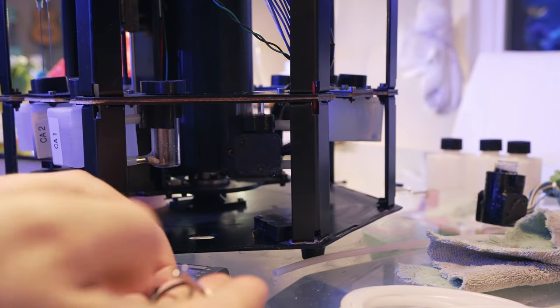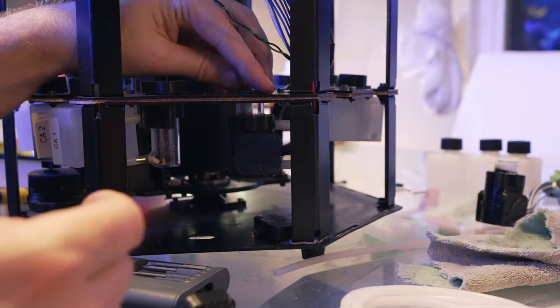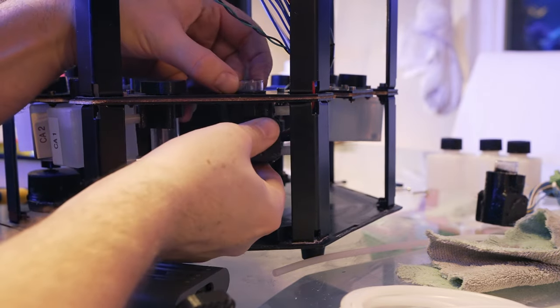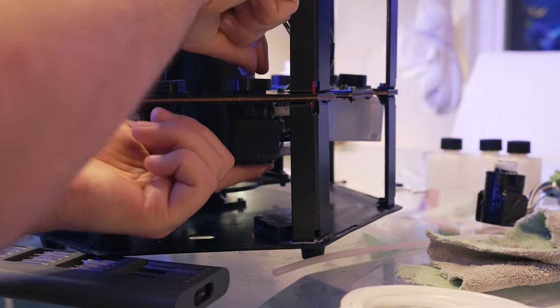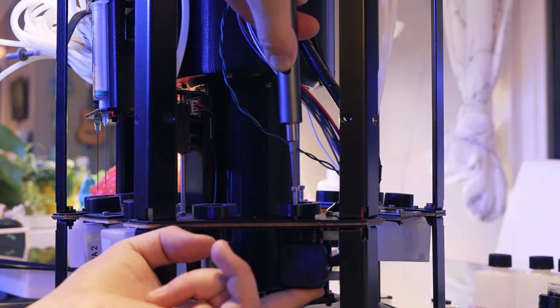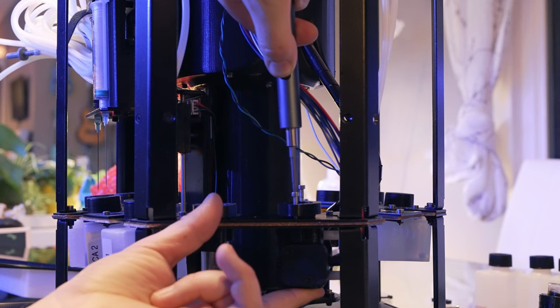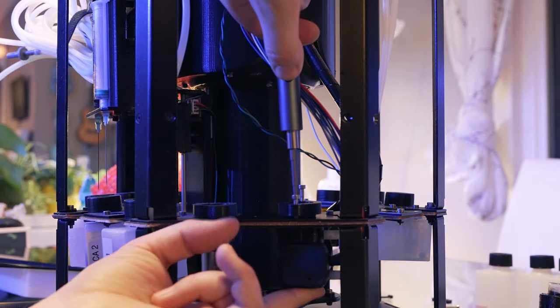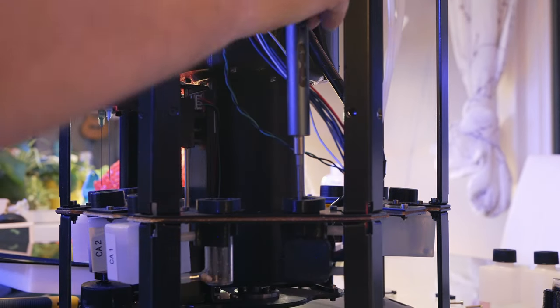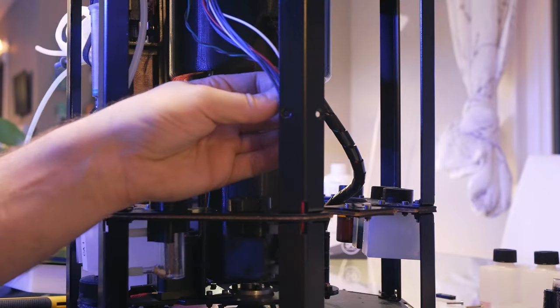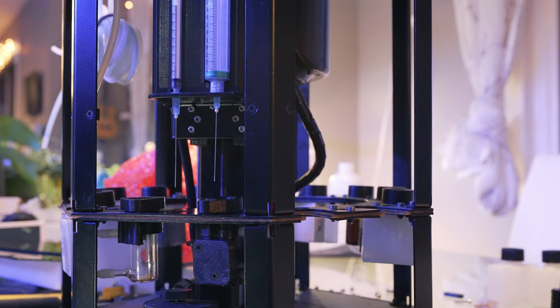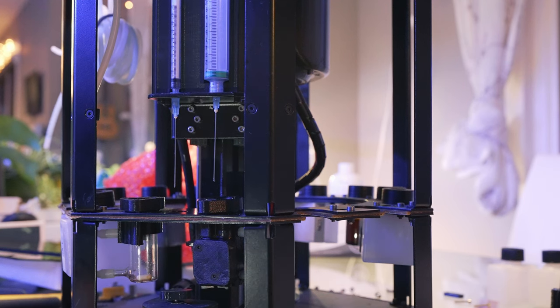So we can screw our reaction chamber back in. And I did receive a new one in this kit with new screws, so we're definitely going to use it and a new O-ring. So that really wasn't that hard to do. It took a little bit of time just getting through all these screws, but the actual routing of the wires and swapping the part was relatively easy. Nice and snugged up. I'm going to put these little wire retainers back in. And the main part of our upgrade is complete.